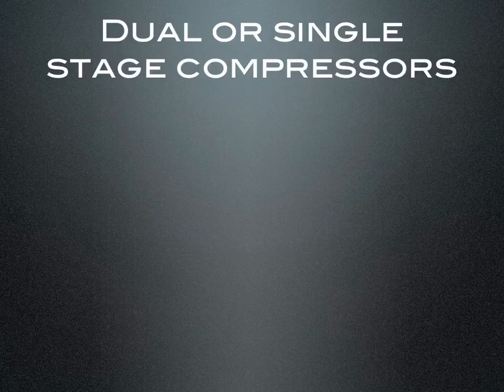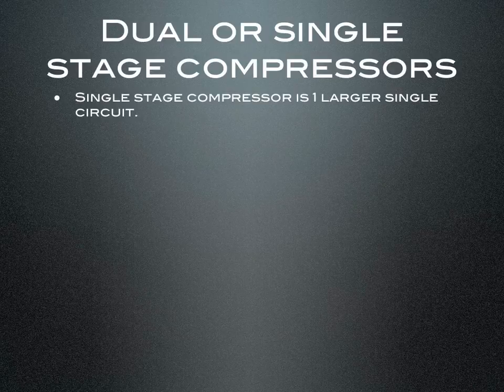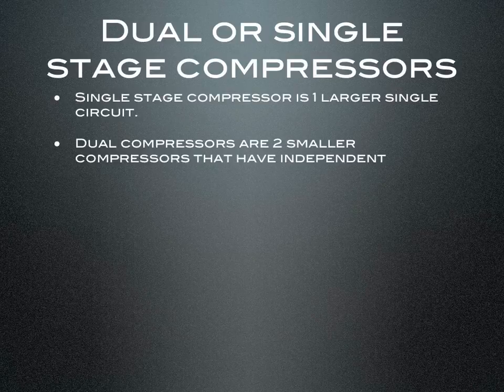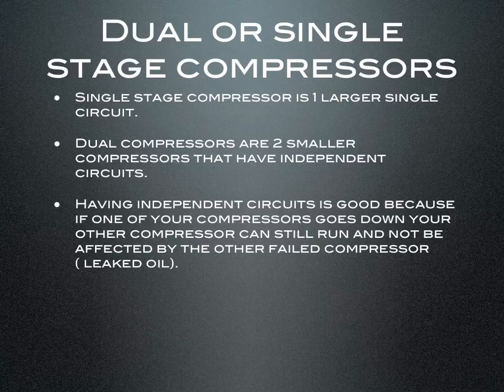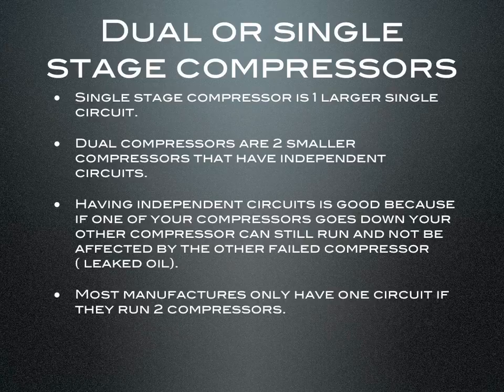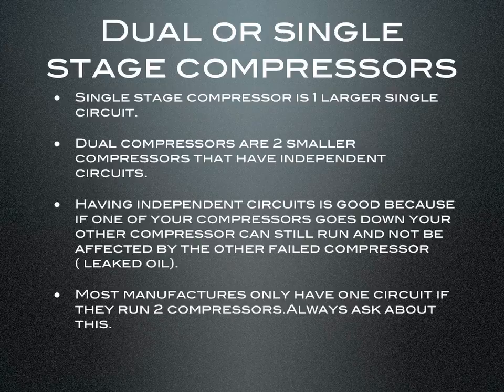Dual or single stage compressors: a single stage compressor is one larger single circuit, while dual compressors are two smaller compressors with independent circuits. Having independent circuits is good because if one compressor goes down, the other can still run unaffected. Most manufacturers only have one circuit even when running two compressors — always ask about this. Our chillers are designed for mission critical applications, so if one compressor goes down with a single circuit, your whole chiller is down. With independent circuits, you'll still have some capacity while the failed compressor is fixed or replaced.